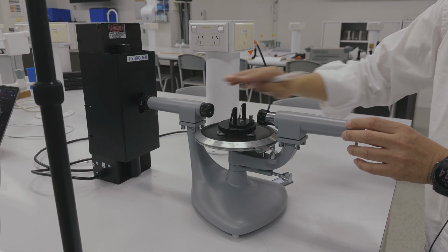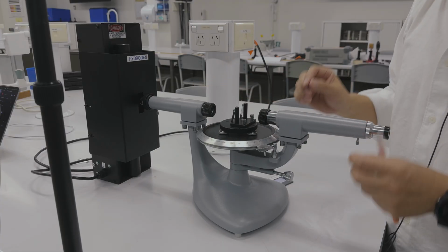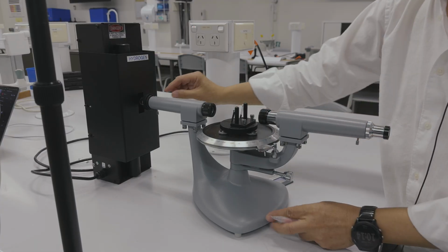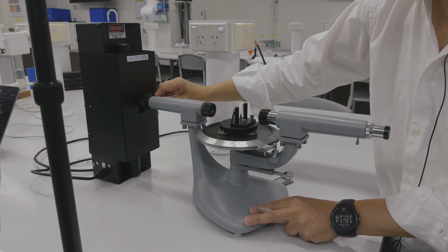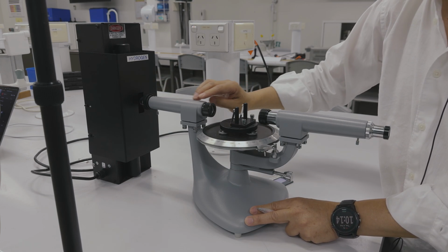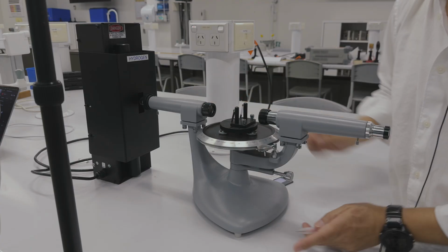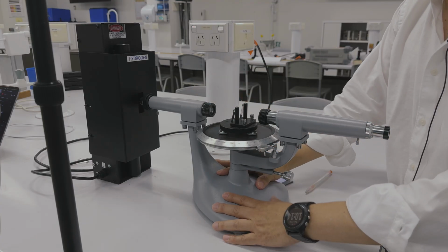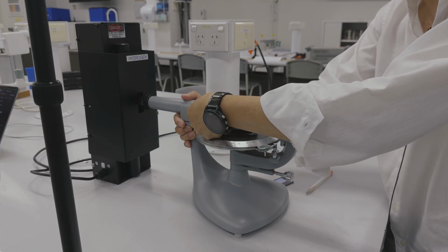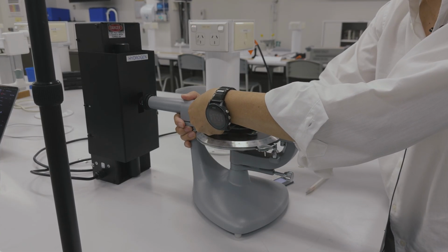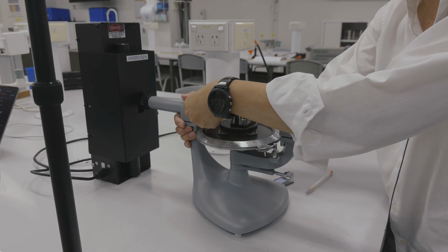Next, we want to optimize the setting. Let's have a look at what we can control. We can control the width of the slit with this knob. We can also control the optics with this one. If you hold this one down, or with your partner, you can pull this one, so you're changing the focus.